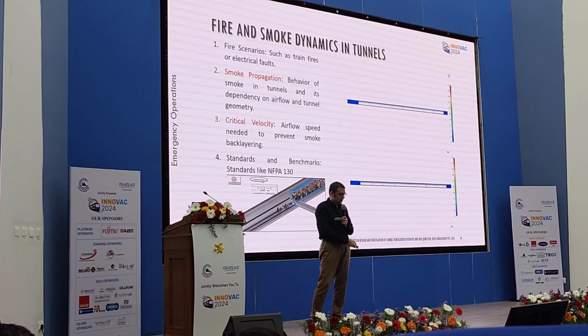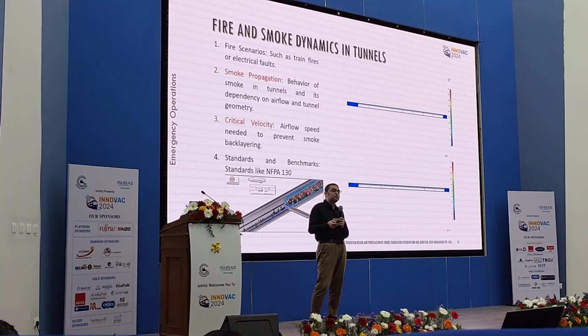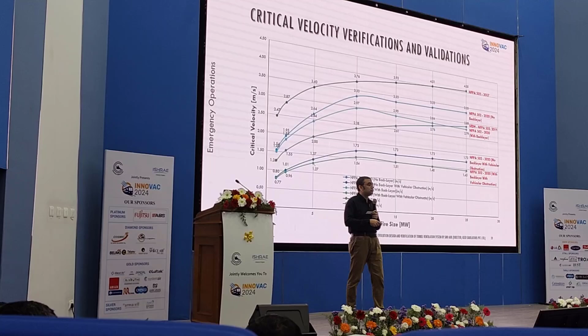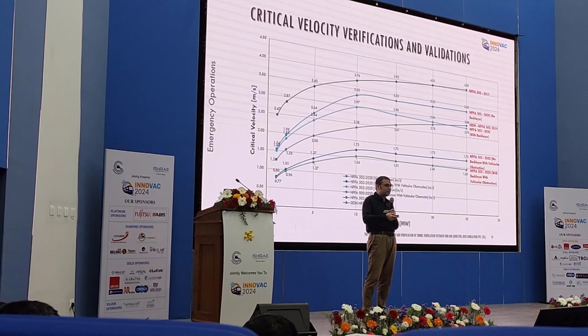I'll speak about critical velocity. Critical velocity is the minimum velocity required to ensure that the smoke doesn't come towards the side of evacuation. Here are some different codes and different megawatts, showing what velocities we eventually have to design for. If I design for say 3.5 meters per second, I'm safe in most codes. For 3 to 3.5 meters per second, I can handle 20 megawatts of fire.